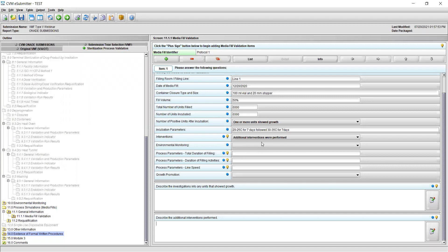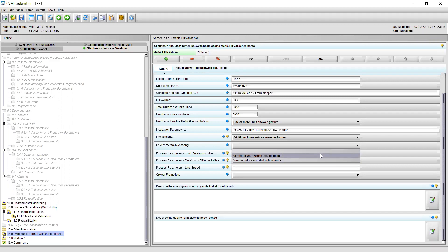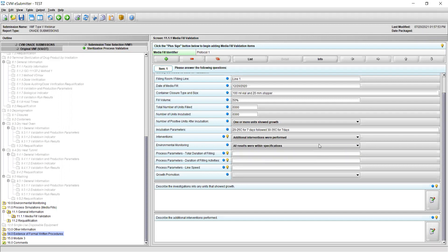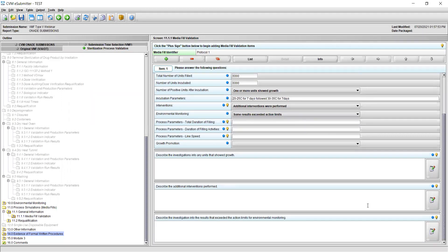In field 10, state if the results of the environmental monitoring during the media fill were within specification by selecting a response from the drop-down menu. You may select either all results were within specifications or some results exceeded action limits. If some results exceeded action limits, a new field will appear asking you to describe the investigation into those results. A summary of the investigations should be provided, results for resampling if performed should be included, and corrective and preventative actions should be discussed.